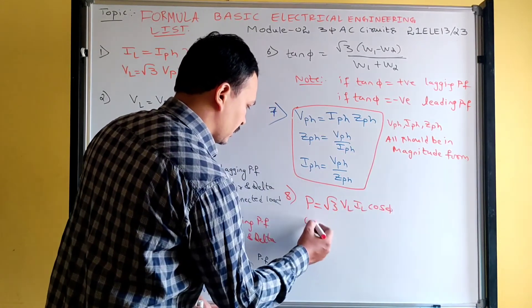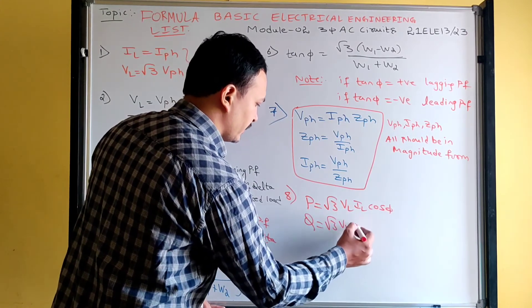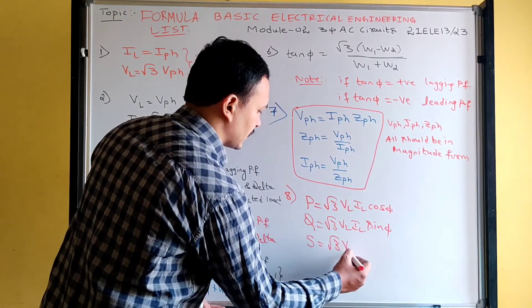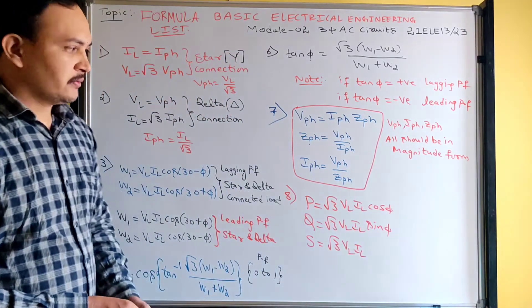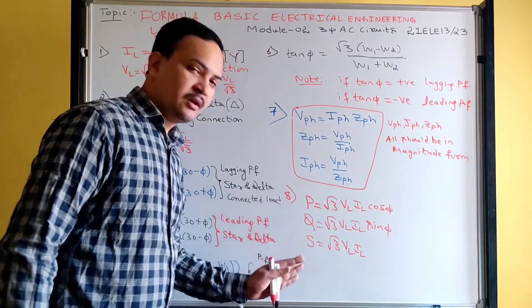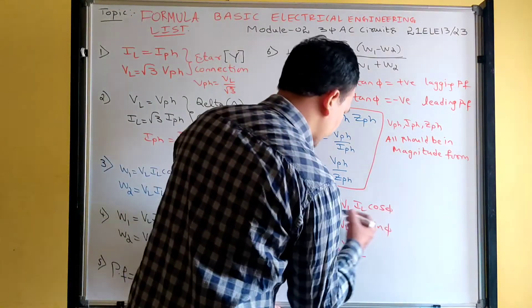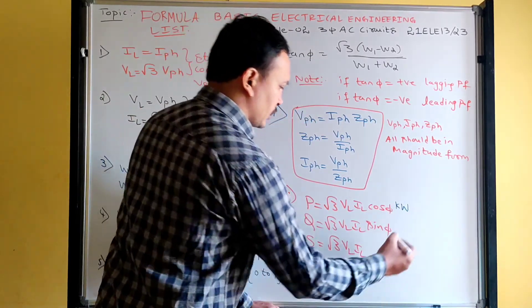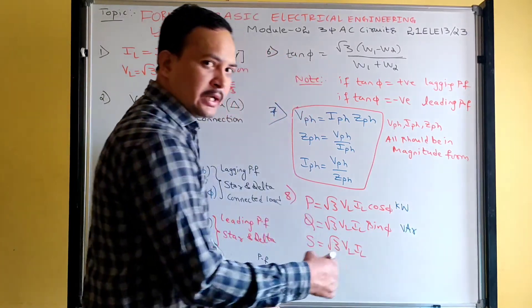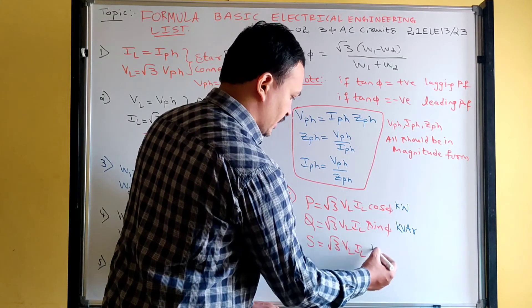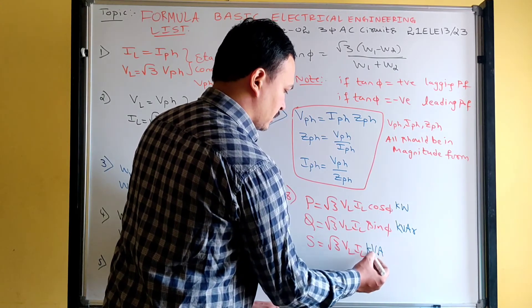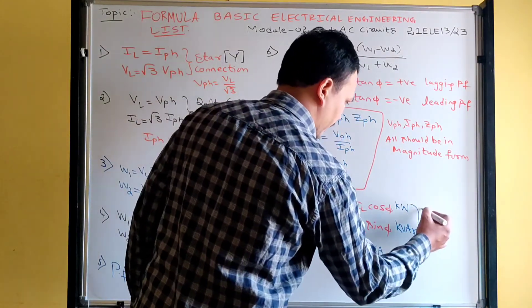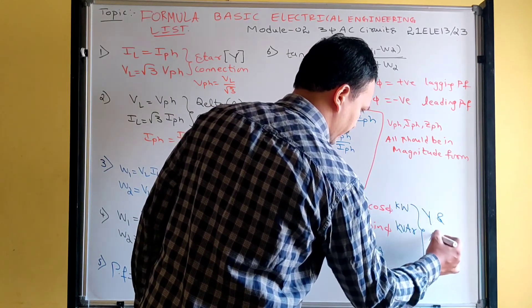Active power formula: P = √3 · VL · IL · cos φ. Reactive power formula: Q = √3 · VL · IL · sin φ. Apparent power formula: S = √3 · VL · IL. All these formulas are valid for both star as well as delta connection. Units: active power in watts (kW), reactive power in volt-ampere reactive (kVAR), apparent power in volt-ampere (kVA).